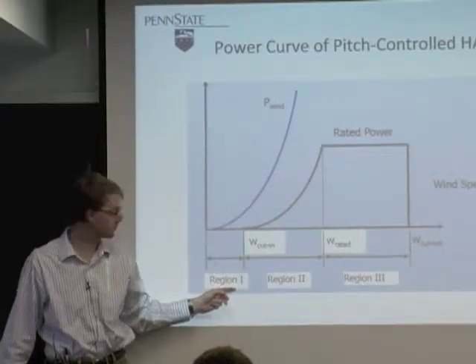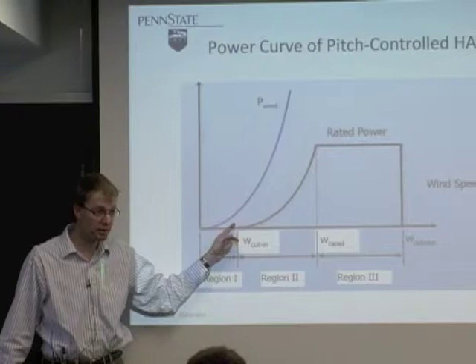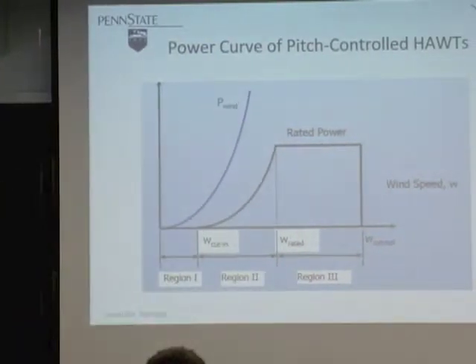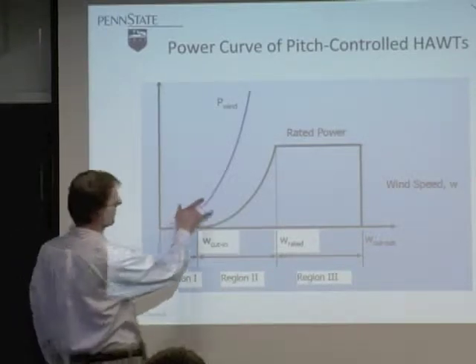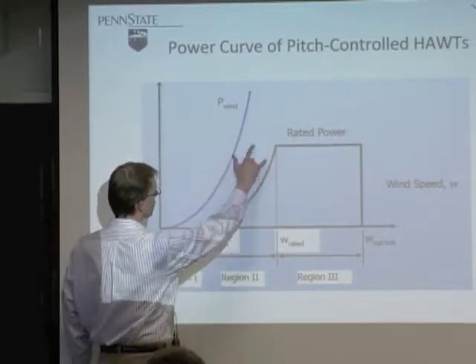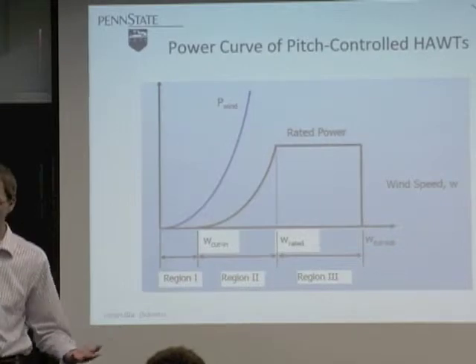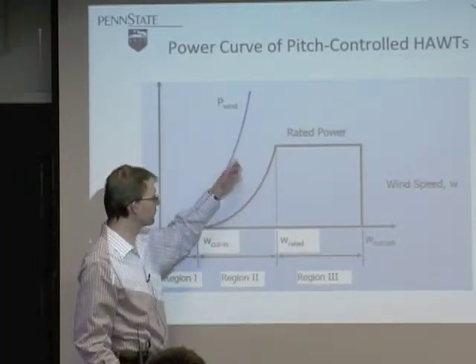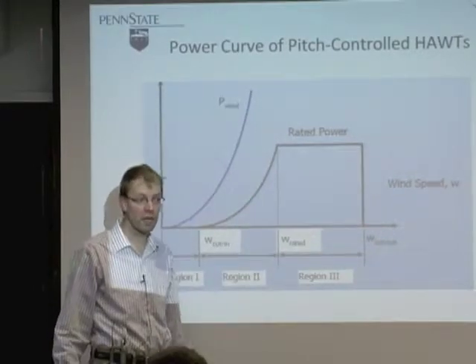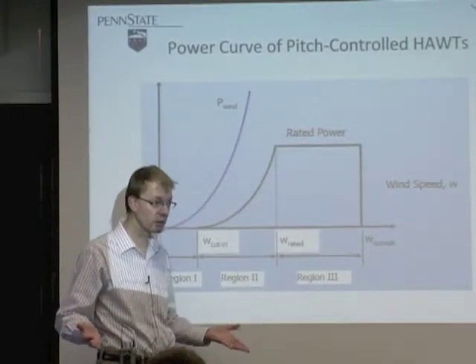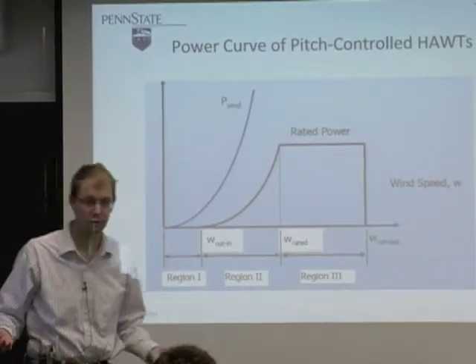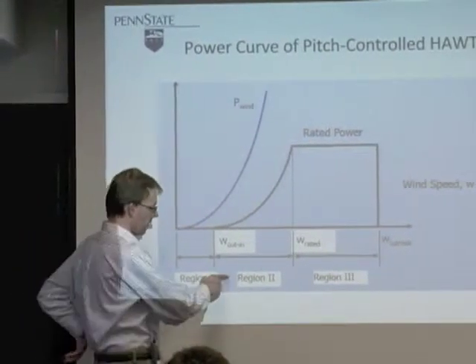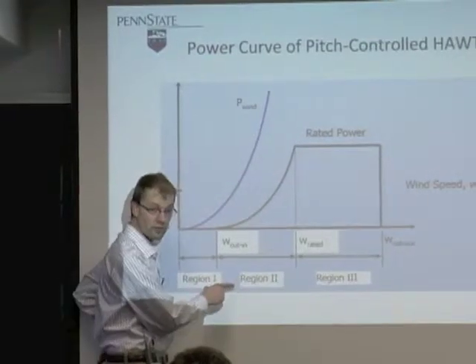Nothing's happening. Then, once the cut-in wind speed is reached, power ramps up, and you can see it's in an almost parallel slope to the power that becomes available with the wind speed itself. But it's only a certain fraction of that amount that a wind turbine rotor can actually capture — and we're going to learn about how much that is. That region is called Region 2.